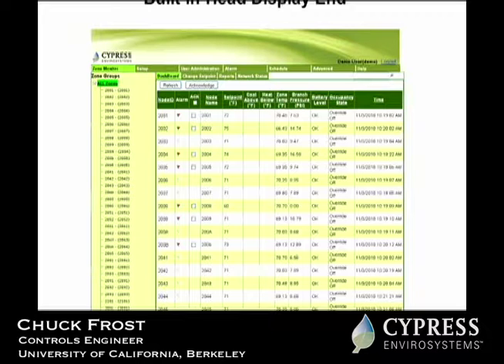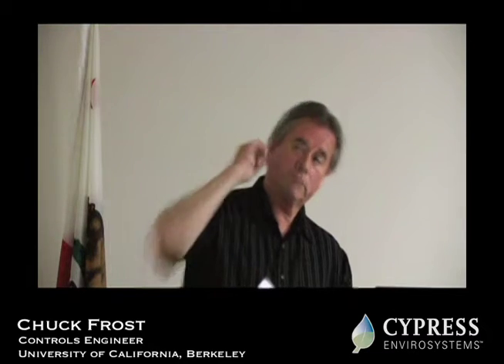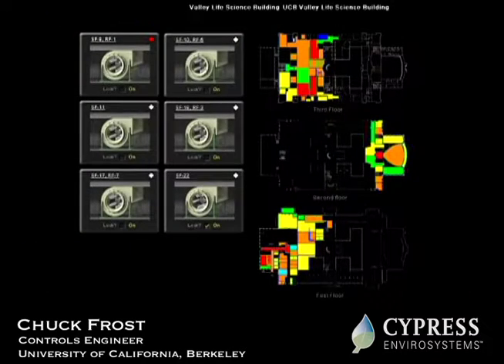I just grabbed these shots of the EMS system. Automated Logic has a unique thermograph feature where you can see your floors — that's what we're seeing here, where we put thermostats in this particular building. There's a total of 73, along with the air handlers we're controlling. We put VFDs — variable frequency drives — on the air handlers to control the speed.